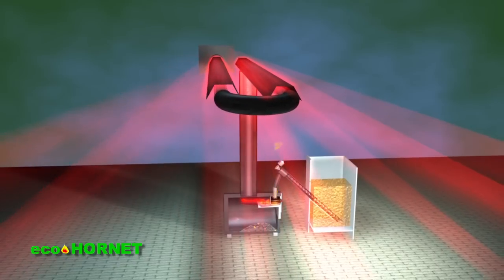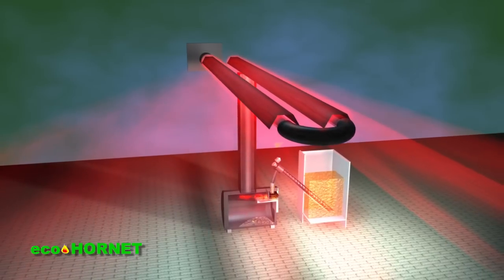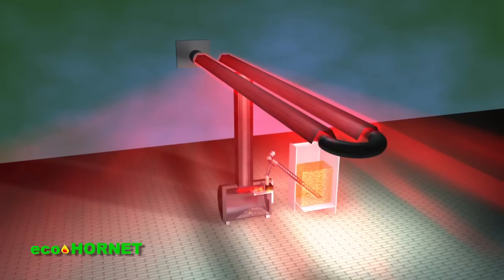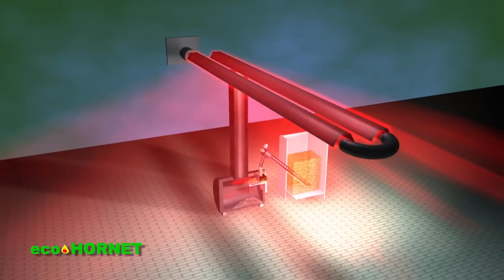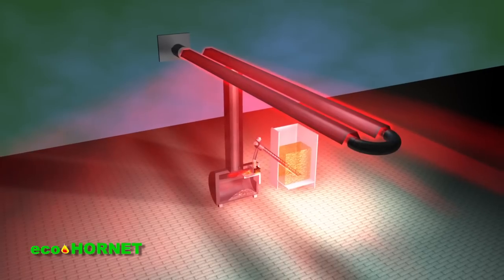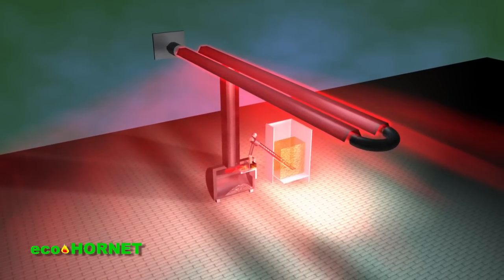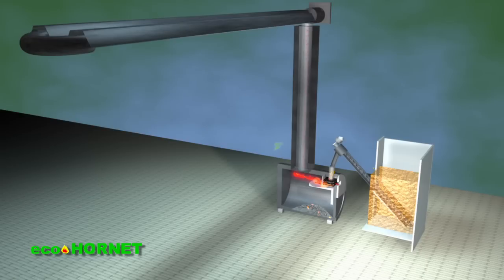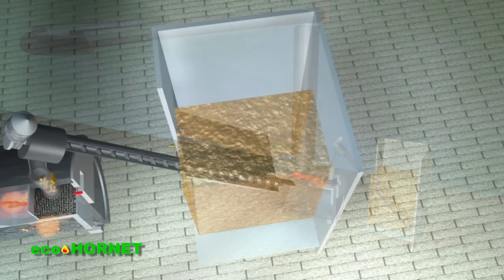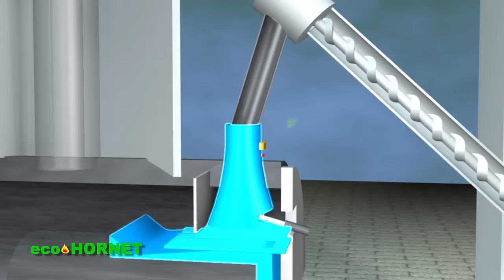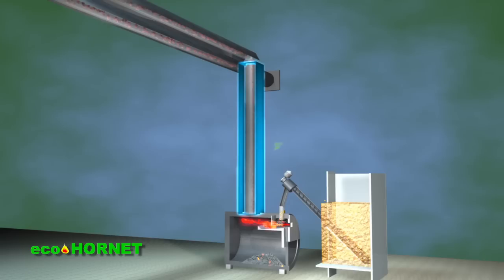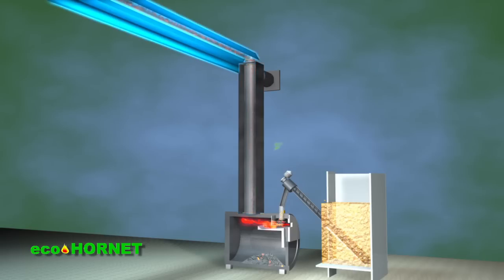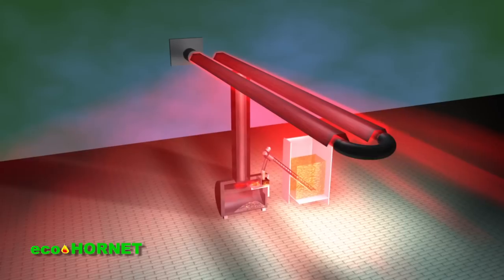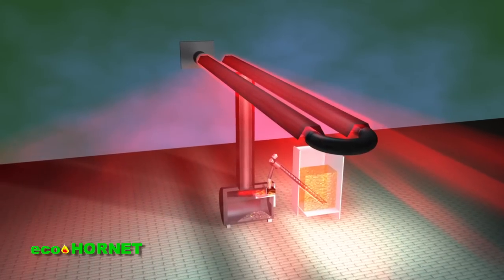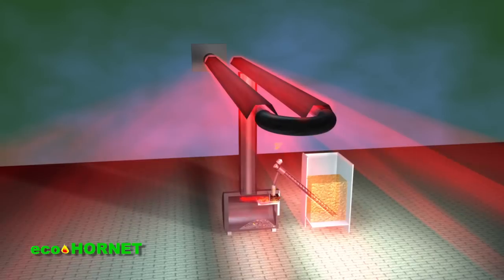The lack of ash particles and of smoke from the burned gases and the temperature at which combustion is achieved ensure the transmission of heat from burning pellets through radiant tubes, maintaining the operating parameters constant without needing to be cleaned. The radiant tube burner system manufactured by Eco-Hornet consists primarily of the following: pellet bunker, worm gear, feeding tube, combustion chamber, insulated tube for the circulation of burned gas, radiant tube with projector, exhaust. The size of the burner and the dosing method for combustion air and secondary air allow the users to control the temperatures required for the optimal operation of the radiant tubes.